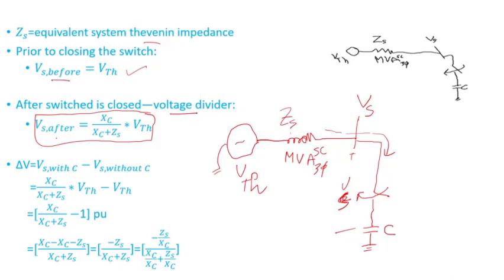The voltage difference is VS with the capacitor bank switched in minus VS without the capacitor bank switched in. If you substitute each term with its equation and write it in per unit — ignoring V-Thevenin — you get this term. Then putting both sides on the same common denominator, XC cancels out and you get negative ZS divided by XC plus ZS.